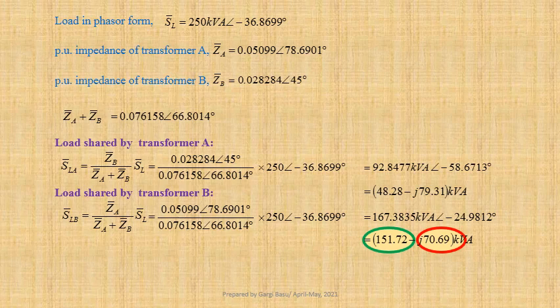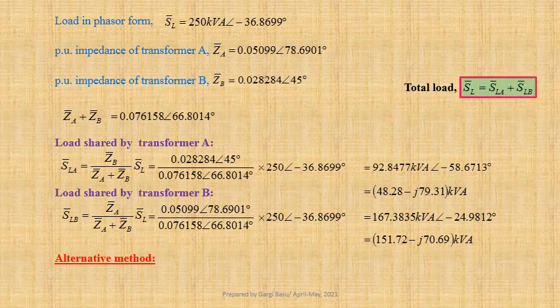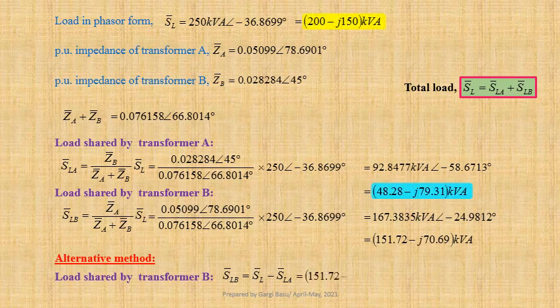Let us now determine load shared by transformer B using alternative method. We know that total load SL equals SLA plus SLB. Therefore, expression for load shared by transformer B, SLB equals SL minus SLA. SL can be expressed in rectangular form as 200 minus j 150 kilovolt ampere. Using values we get SLB equals 151.72 minus j 70.69 kilovolt ampere, that is equal to 167.3835 kilovolt ampere at an angle minus 24.9812 degree.